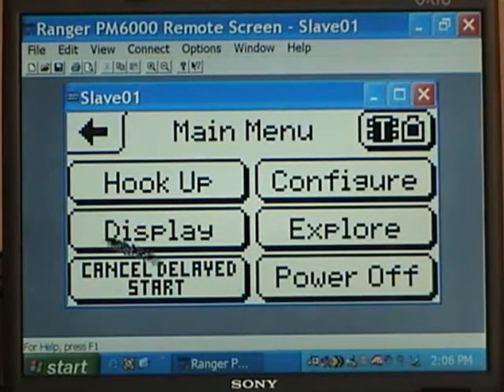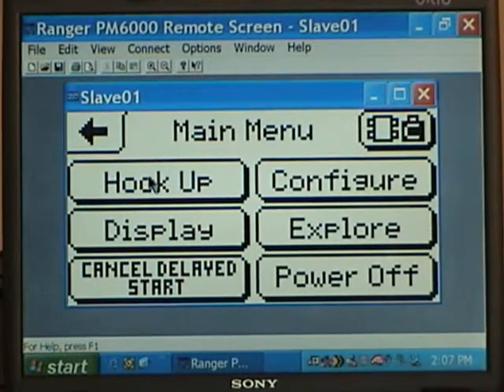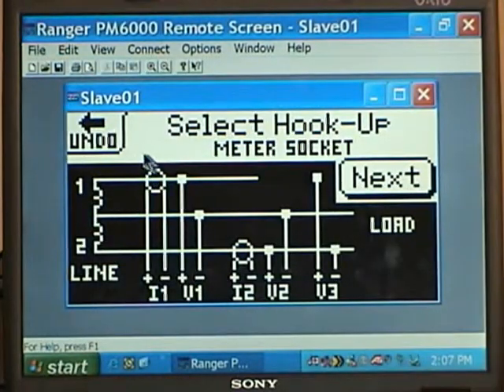And we'll go through each one of these buttons here for you. First of all, this is a start button here, and this is a power off button here. Those are pretty self-explanatory. The hookup button, if we click on that, it shows us a split phase, L1 to neutral, L2 to neutral. Here's your voltage hookup for L1 to neutral, your voltage hookup for L2 to neutral, and your L1 to L2 voltage hookup. And then here is a description showing one of the Rogowski coils is around L1, the other Rogowski coil is around L2. It is the only hookup available, of course, on a meter socket logger.